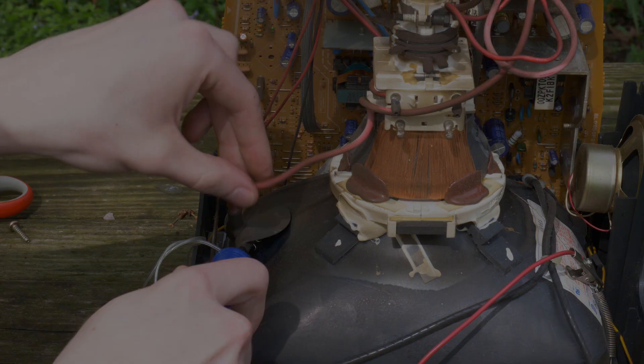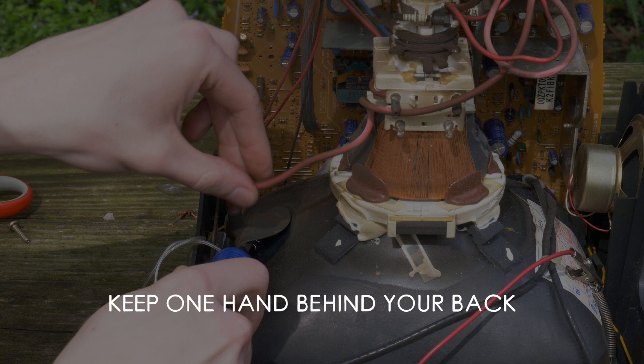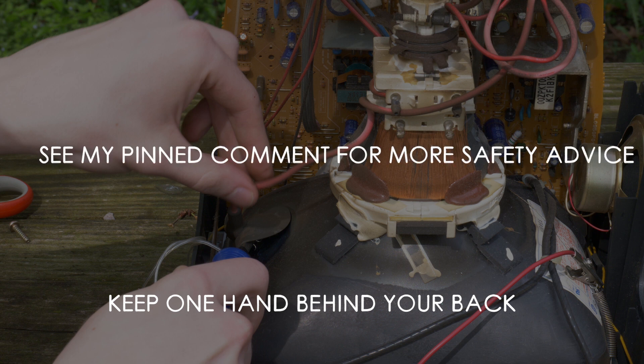Please don't do this. You see how I have my left hand touching the wire and my right hand touching the screwdriver? Always put your non-dominant hand behind your back when working with high voltage. Using one hand minimizes the risk of a fatal shock. Also, just because a wire is insulated doesn't mean it can't shock you.